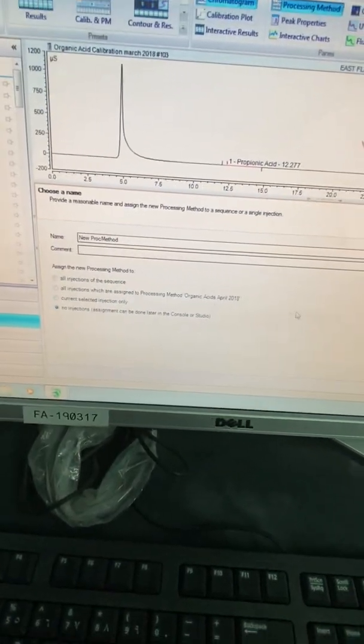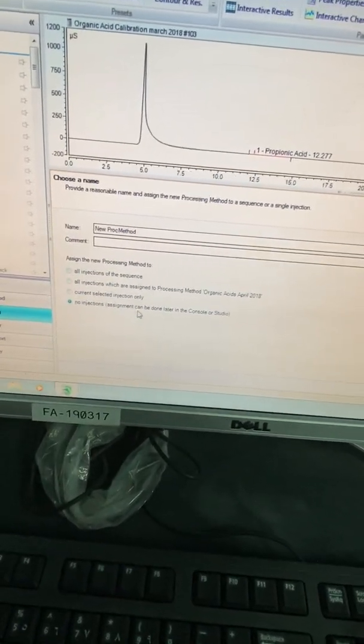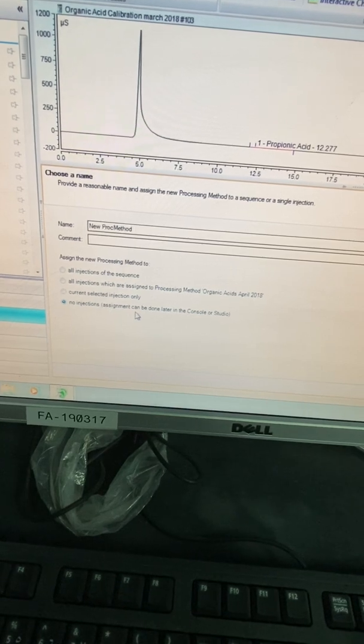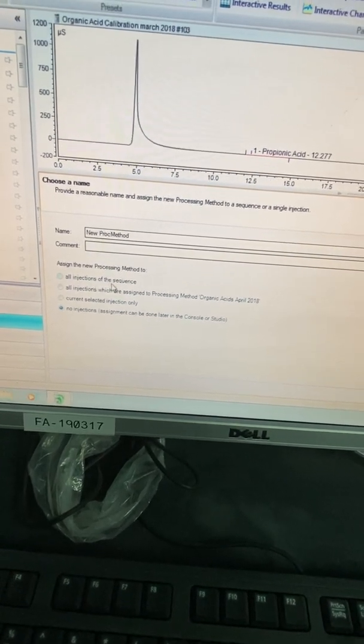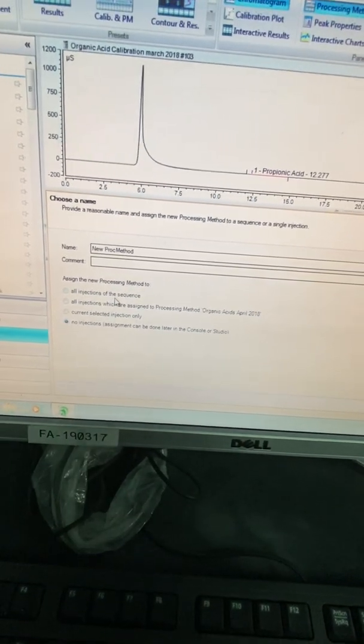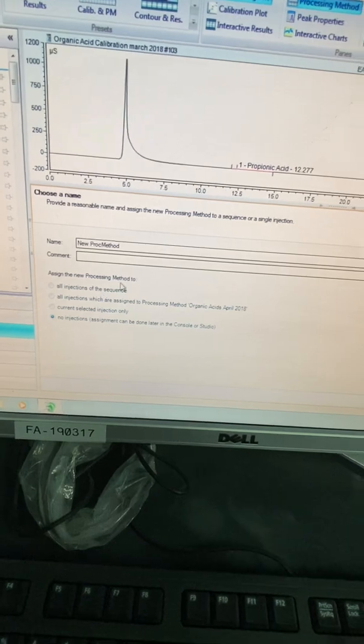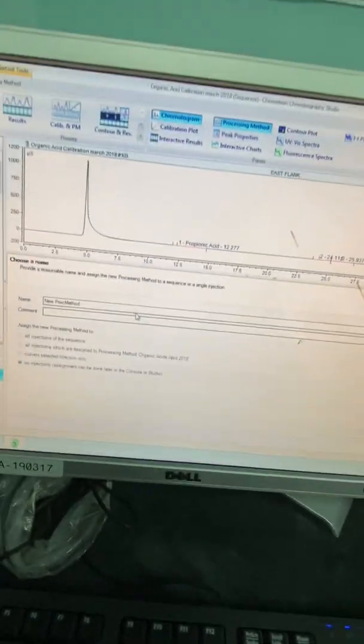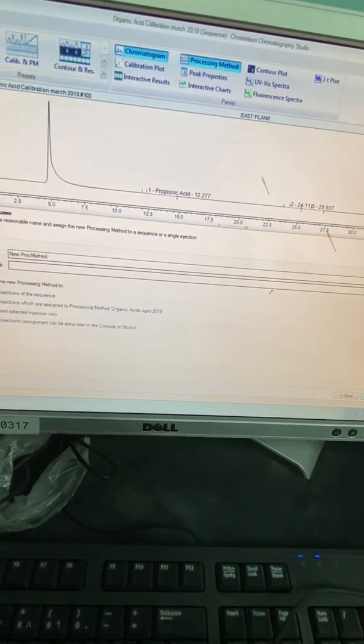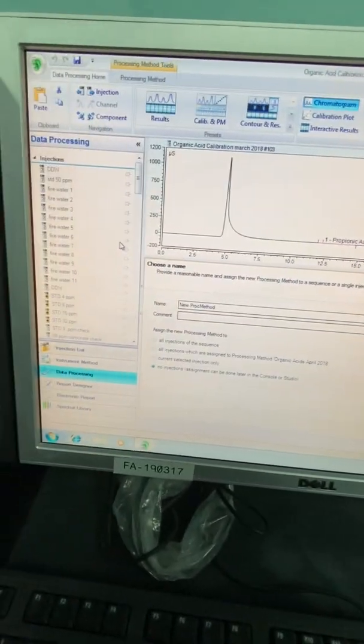It will be similar, you have to choose which software or which type you want to do. Like it's Chromeleon 6. You can press next or some of the software have wizard. Nowadays it will be easy for you. So by adding next, it will ask you the method name. All the injection. In this case, there is no injection is done there. Or you can select, if you injected the blank and the standard, you have to select all the injection in the sequence. Finish, you will name your method. So, how to check the calibration or to do the calibration?